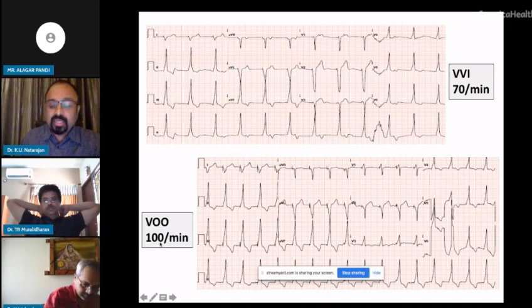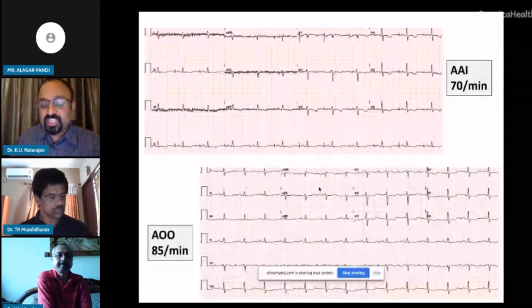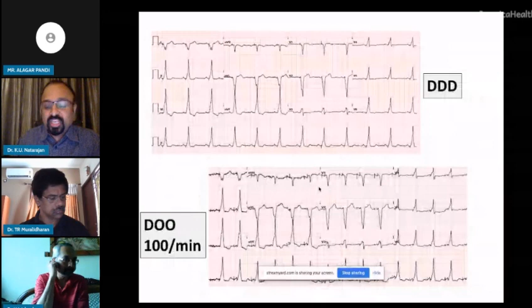That's why I told you, you should know your pacemaker. What is the pacemaker? What are the settings of the pacemaker? What is the make? Which company's pacemaker? What is the expected behavior of the particular pacemaker based on the industry specifications? All this you should understand before you interpret and venture into making a diagnosis of normal or otherwise pacemaker function. This is just a dual chamber pacemaker shifting into a DOO mode with the magnet kept. So the last question is, is the pacemaker functioning normally? The 3 functions of the pacemaker are: a pacing output should be delivered.